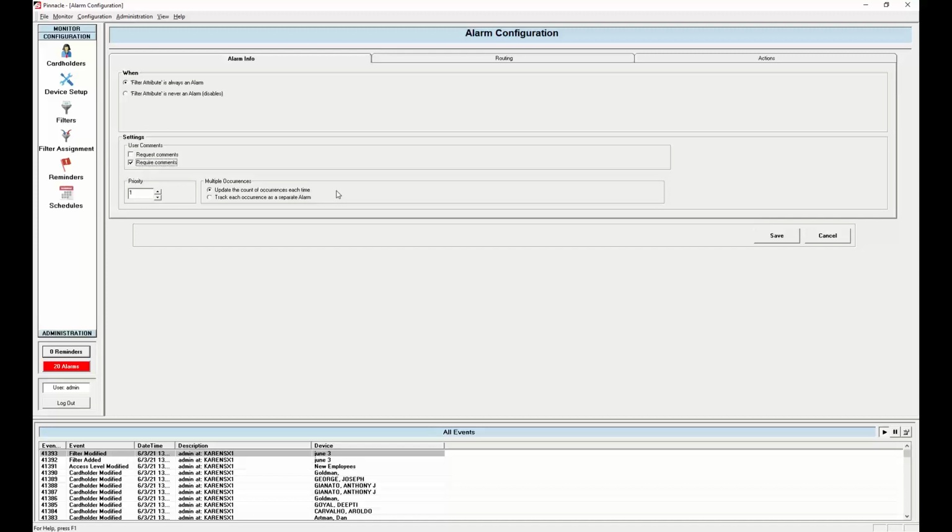So an example where you might use time and not display it every single time is maybe you've got a device that's wired in the system. There was work being done in the building. A contractor pinched one of the cables. And so now we've got a cable short on one of your contact points. And it's intermittent, happens periodically, very difficult sometimes for a technician to troubleshoot that one.